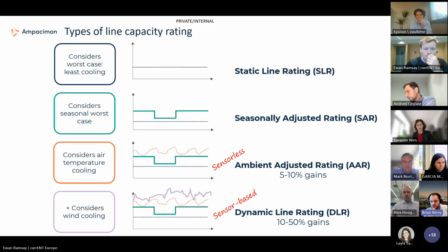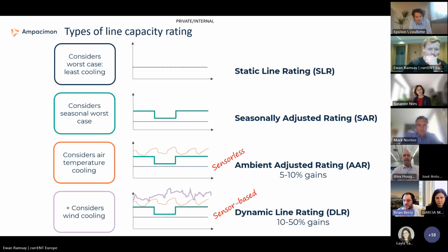Looking at this slide, similar to what Alex was saying, we have different levels of line rating. Typically most utilities in the world are at one or two: static line ratings or seasonal ratings. But we can jump into ambient adjusted ratings where we consider the ambient temperature and get a gain based on that, or go one step further and include the wind for even more gains. The gains you see on ambient adjusted ratings are in the region of about 5 to 10% capacity gains. But the beauty of this is that it's very easy to deploy.